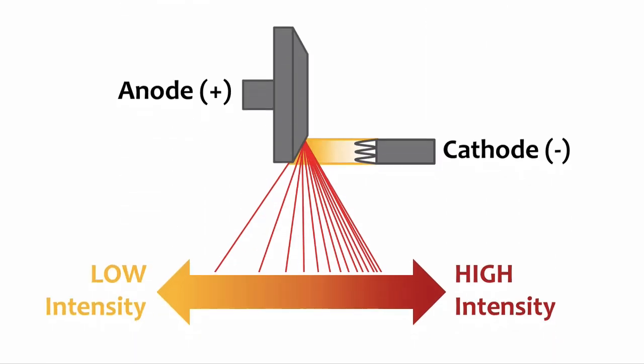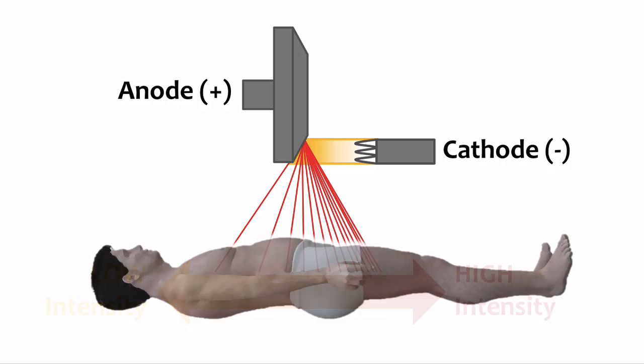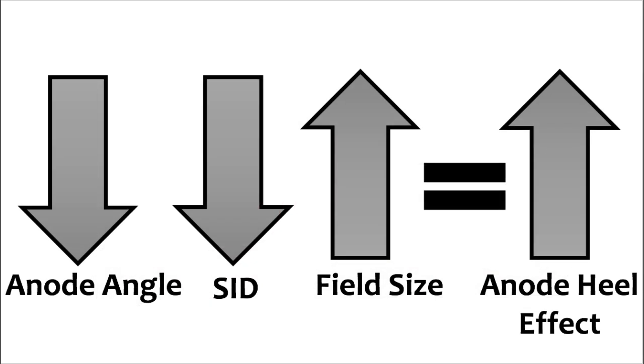In summary, the anode heel effect is the change in beam intensity across the length of the x-ray field. Specifically, the anode side has fewer photons and the cathode side has more photons — the anode side is weaker and the cathode side is stronger. Remember that the heel effect can be used to our advantage by placing the thinnest portion of the patient under the anode side and the thickest portion under the cathode side. Finally, three changes can increase the anode heel effect: decreased anode angle, decreased SID, and increased field size.